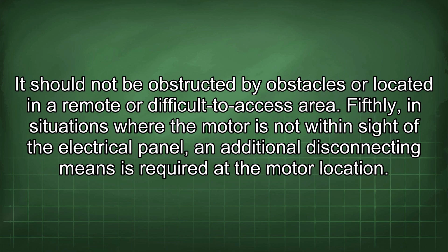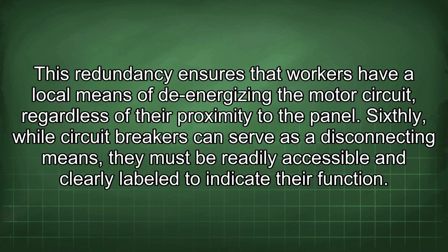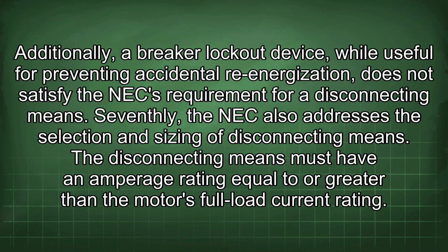Fifthly, in situations where the motor is not within sight of the electrical panel, an additional disconnecting means is required at the motor location. This redundancy ensures that workers have a local means of de-energizing the motor circuit, regardless of their proximity to the panel. Sixthly, while circuit breakers can serve as a disconnecting means, they must be readily accessible and clearly labeled to indicate their function. Additionally, a breaker lockout device, while useful for preventing accidental re-energization, does not satisfy the NEC requirement for a disconnecting means.